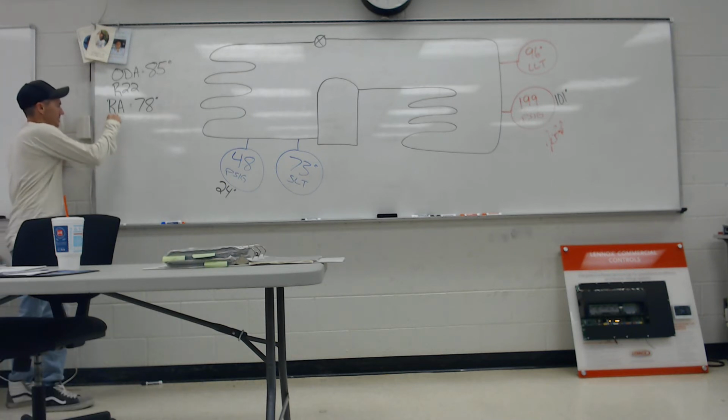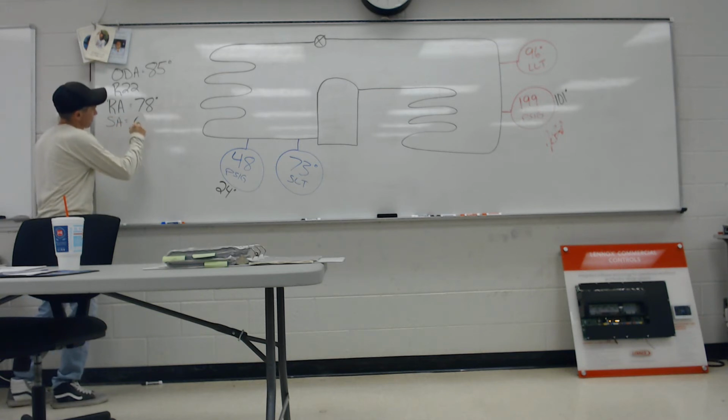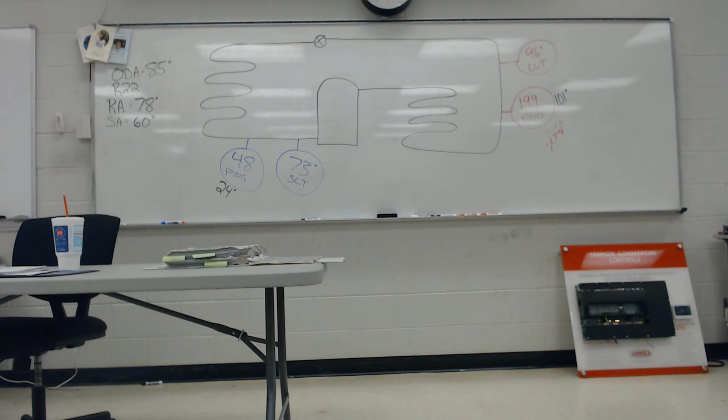But here you go. Here's my supply air temperature. You ready to blow your mind? It's got an 18-degree split. That's good. Sensible.